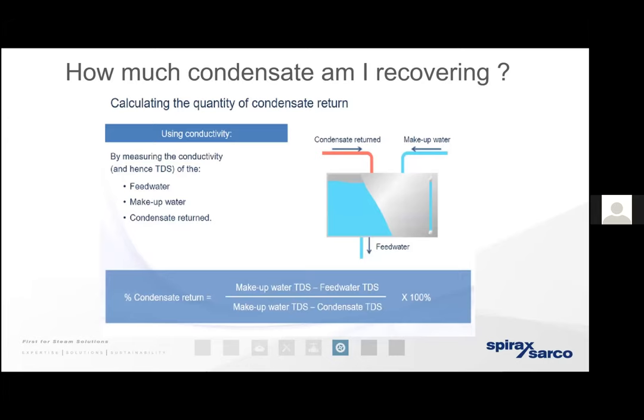If we bring condensate back to the hot well and keep it at a nice high temperature, there are a number of benefits. First, the boiler responds far more rapidly when there's a demand for steam; we consume far less fuel to raise steam. Another key benefit: condensate has already been chemically conditioned — we typically add chemicals to scour out oxygen and non-condensable gases. The more condensate we recover, the more cost savings we enjoy. We can calculate the percentage of condensate being returned by conductivity measurements.